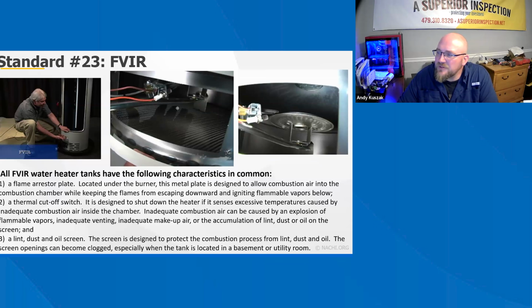If the flammable vapors are present in sufficient quantity to prevent normal combustion, the burner pilot flame is shut down. Should the flammable vapors continue to burn, the flame arrestor plate prevents the flames from traveling backward and igniting vapors outside of the combustion chamber. The calibrated multi-purpose thermal switch recognizes this and shuts down the pilot and main burner. This switch also deactivates the burner and pilot in the unlikely event of restricted airflow caused by severe lint, dust, or oil accumulation on the arrestor plate.